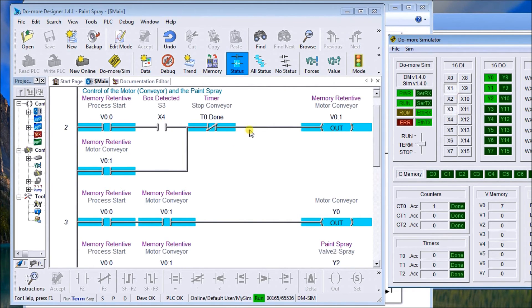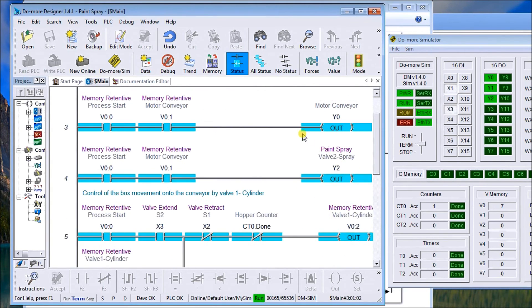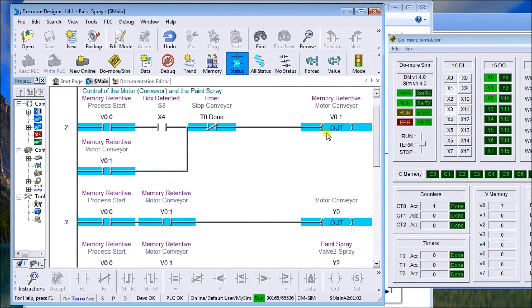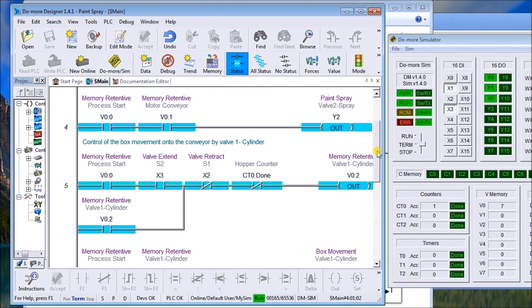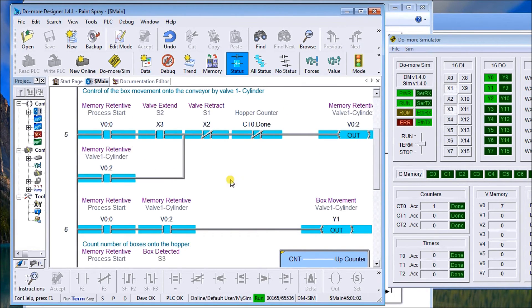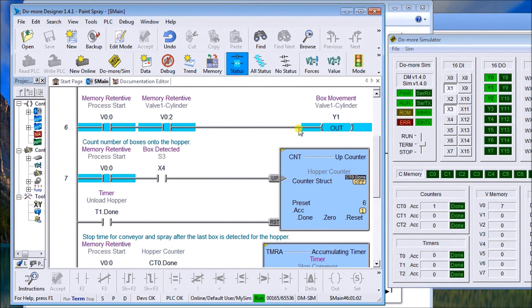Then it will move over and also the paint spray. So there's our motor and our paint spray. You'll notice that I use internal relays here. They're memory retentive, so that if we stop this or we lose power to the PLC, it will continue to run.